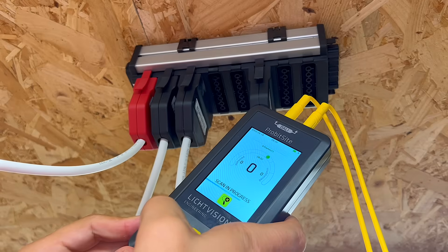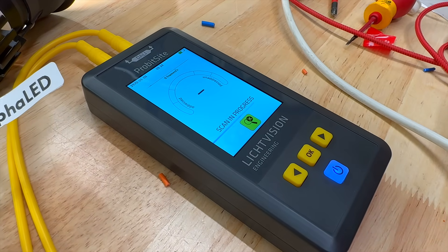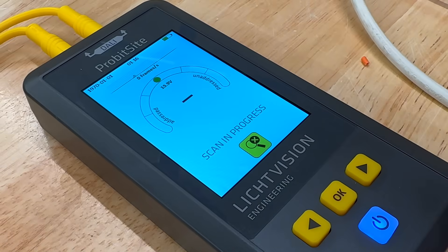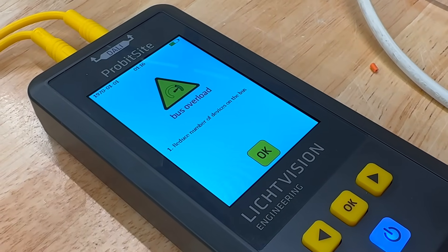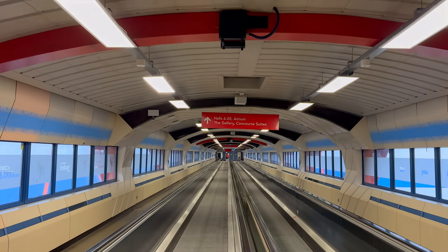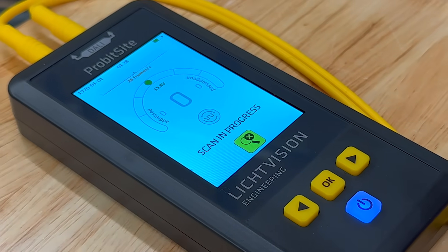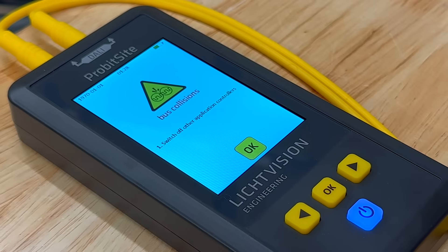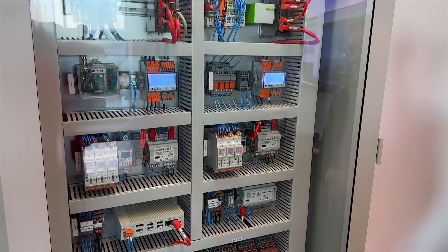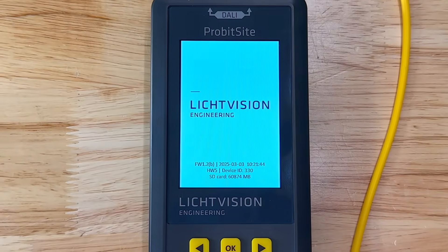Before we dive deeper into what's actually happening on the DALI bus, there are a few other wiring and installation issues we can clear up. The ProbitSite will identify if there's a short circuit on the wiring. It will also tell you if too many devices have been connected to the bus - an easy mistake to make, especially on installations using modular wiring with multiple groups of the same type of lighting fixtures. The ProbitSite can also detect if an application controller is still connected and sending control signals - in that case it will need to be disconnected before testing.